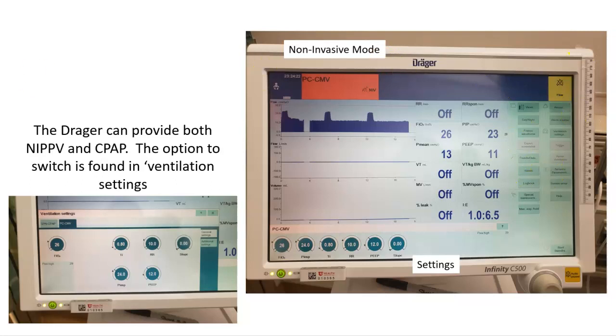Over here you can see once we're in that standby, in that non-invasive mode, we have CMV, which is our Nippy setting, and then CPAP. So it says spontaneous CPAP and pressure control CMV. That is the Nippy. CPAP would be a CPAP mode down here, and then you can see NIV right here, and this orange box will indicate that we are in a non-invasive mode. Also, that we don't have the flow meter in line. This is saying no flow meter.